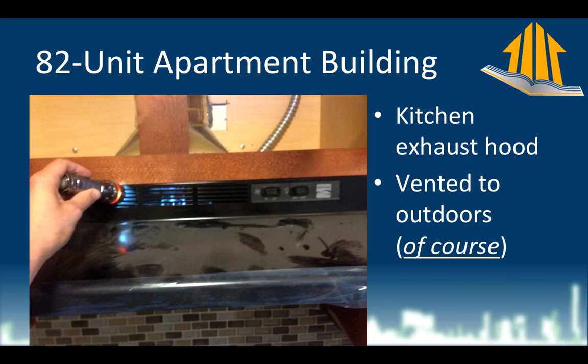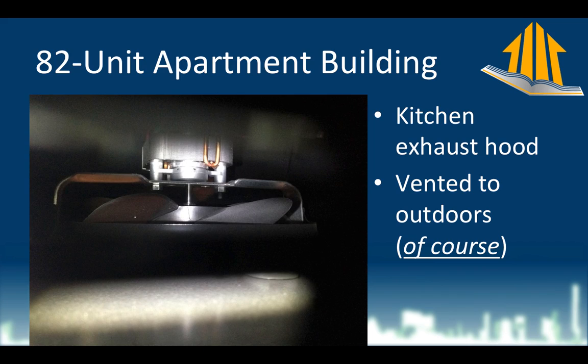So while I'm getting ready to do this test, I've got my anemometer out and I'm about to test the flow. I feel something blowing on my forehead. What could that possibly be? We've spent all this money and time and effort trying to get this thing exhausted outside. So I pull out my flashlight and I look into this little grate on the front there, and I can clearly see through that grate the fan. If I can see the fan, it is most definitely going to be blowing in my face when it turns on.